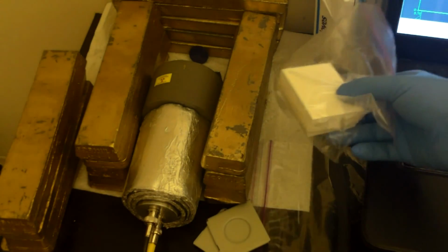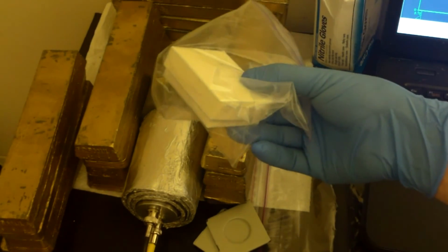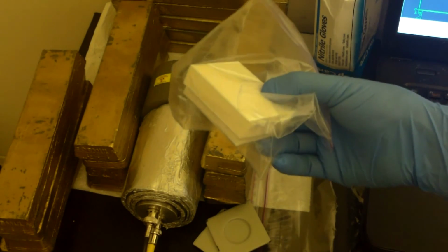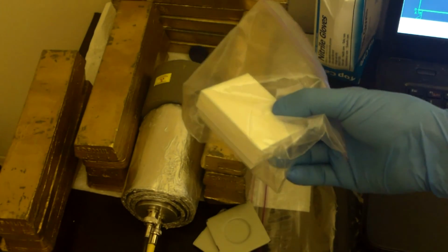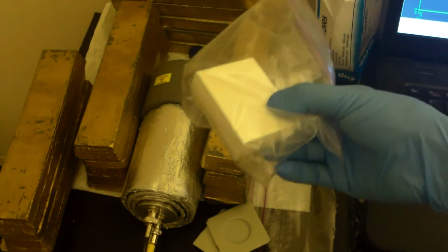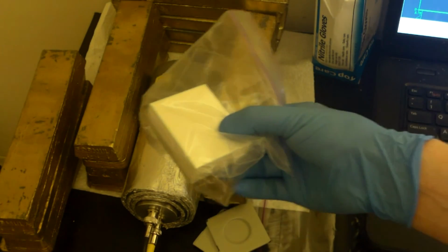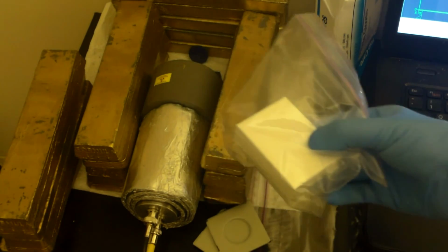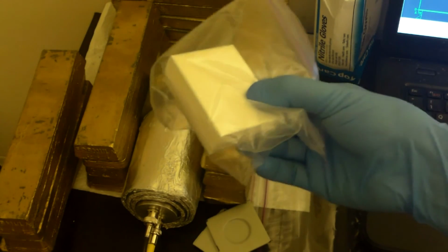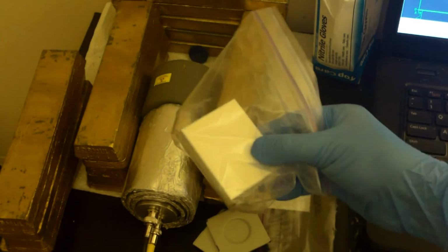All right, we're ready to test now. We're going to start with this little box which contains a rock, probably uranium, probably thorium, could be potassium. Between uranium, potassium, and thorium, the highest energies we're going to be looking at were from potassium. So this should be lower than that, so it should fit in nicely with what we've already calibrated.